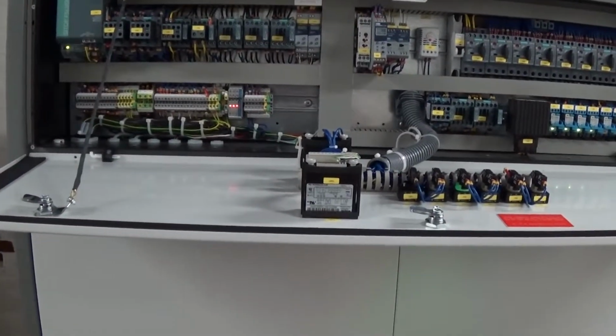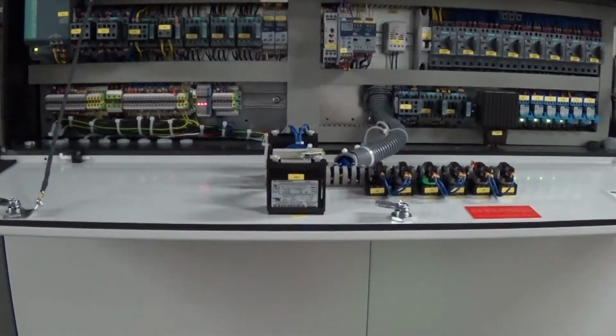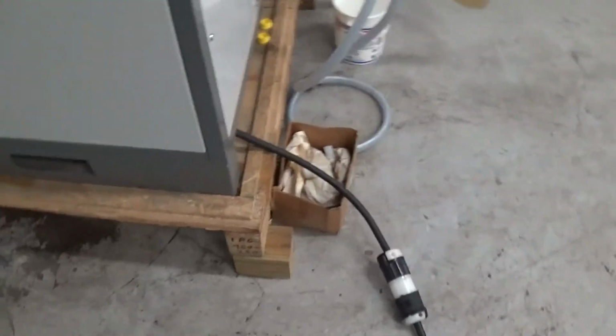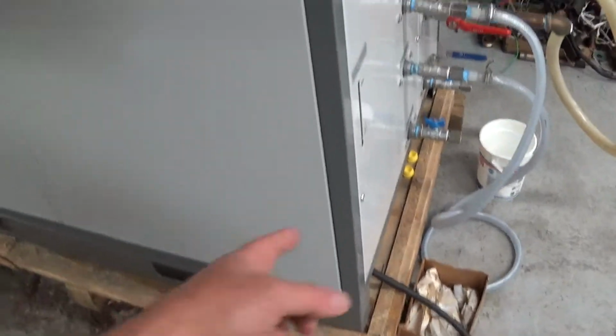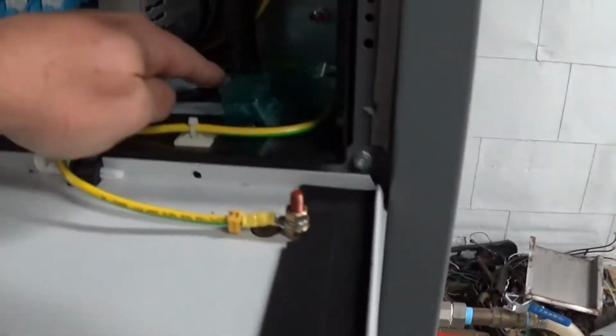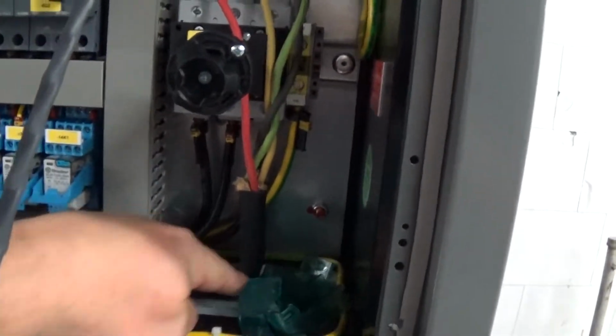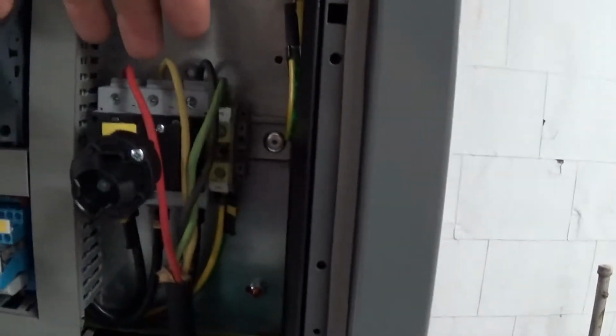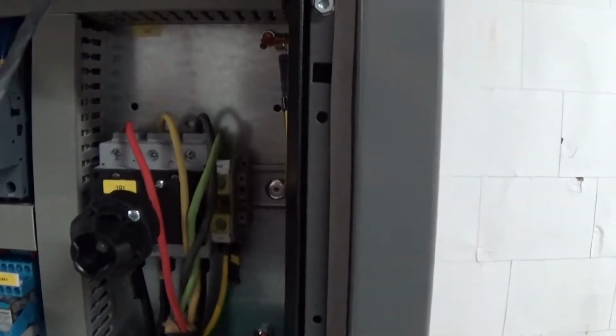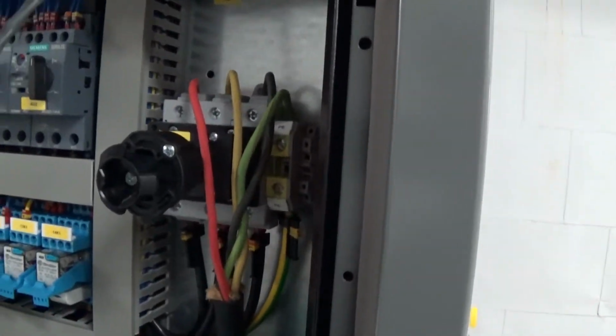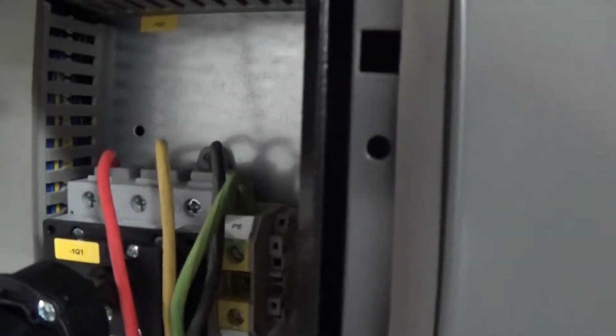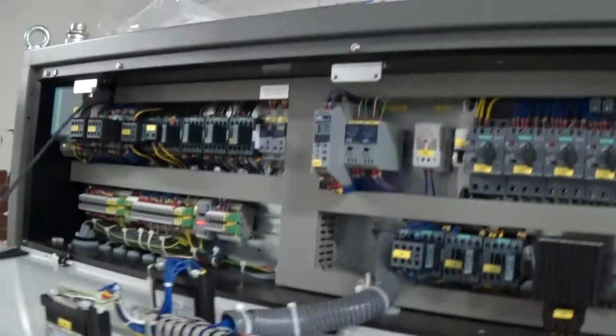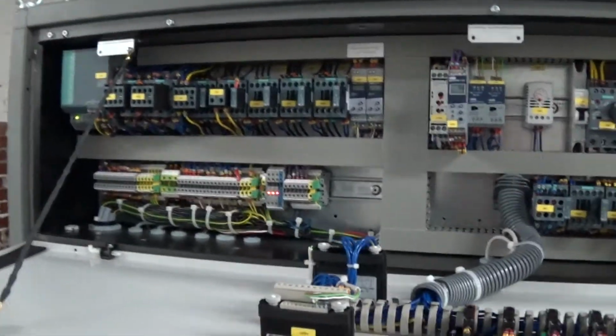If upon startup the phase rotation is going in the wrong direction, disconnect your incoming power. Your incoming power comes in through a cable here, goes up through the unit, snakes up behind here and up to this little conduit or hole, and then your 3 incoming powers go into the top of this disconnect here, and your ground off to the side. That is where, if the rotation's wrong, you disconnect your power and change any 2 of those leads here. Don't do anything with any of the direct pump contactors or overloads inside this cabinet.